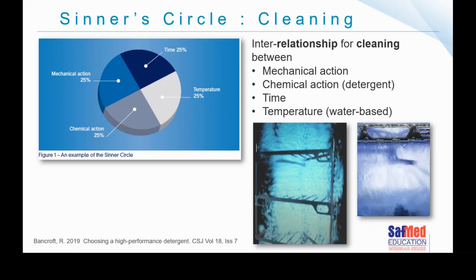When you're cleaning manually, the mechanical action comes from the rubbing and scrubbing using a brush or cloth. In an automated washer disinfector, that mechanical action comes from the water — the pressure, the force of the water. If you look at the images on the slide, you'll see different images displaying the force of water inside a washer's chamber. That's often referred to as impingement, or the impingement value. We need all of these elements in place as described in Sinner's circle.